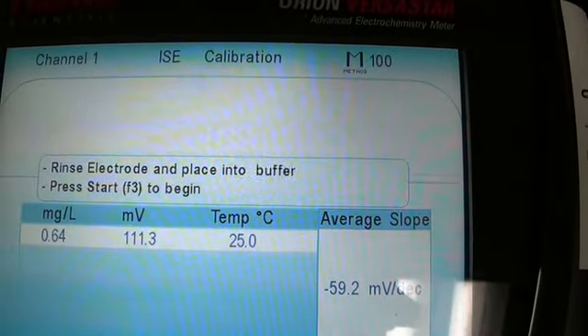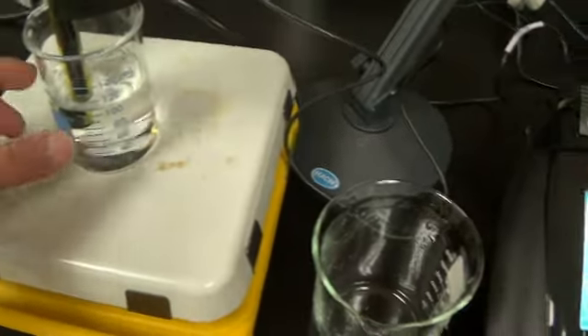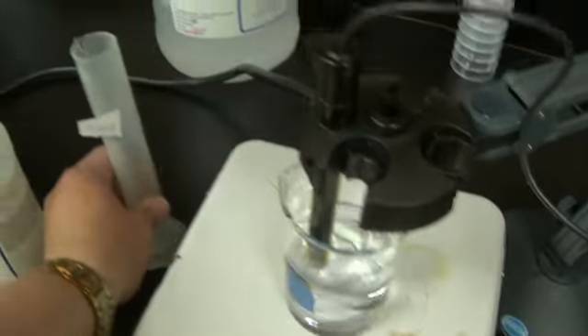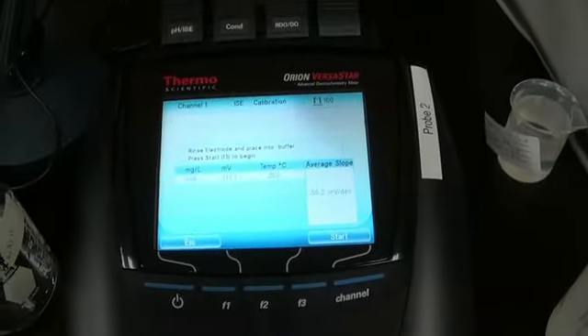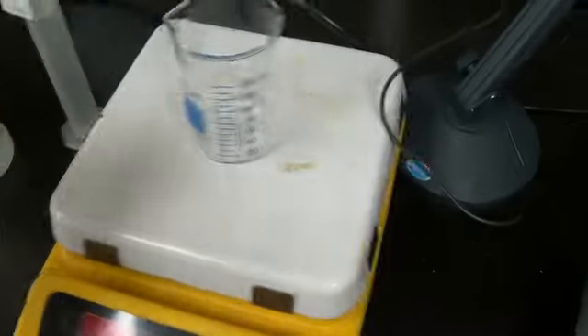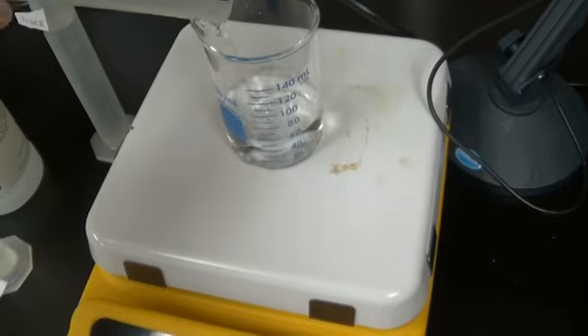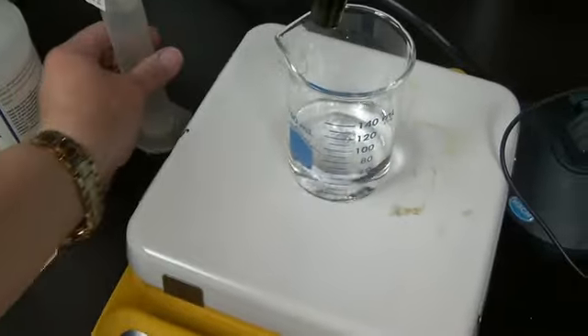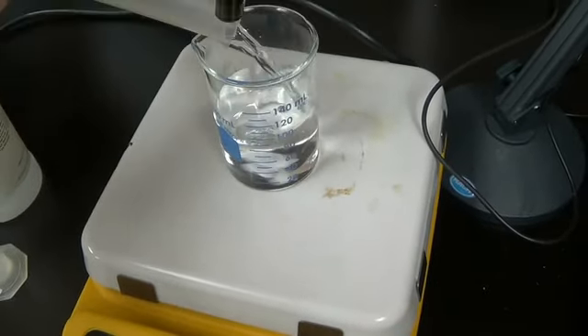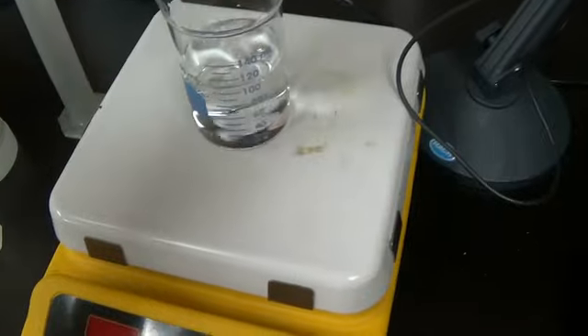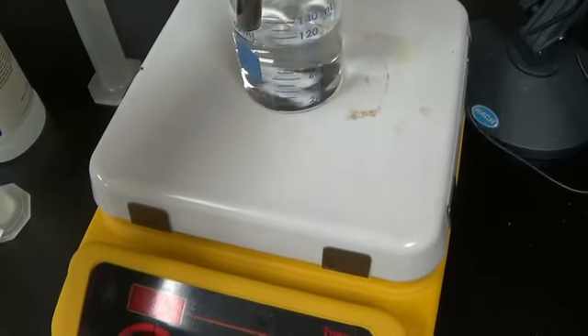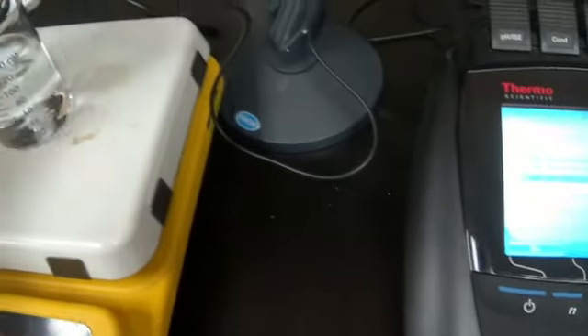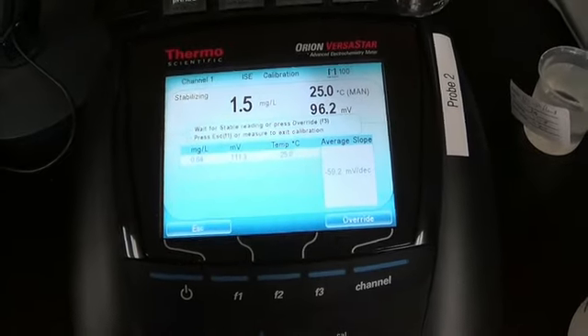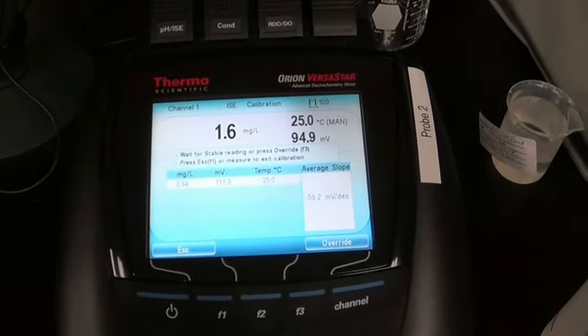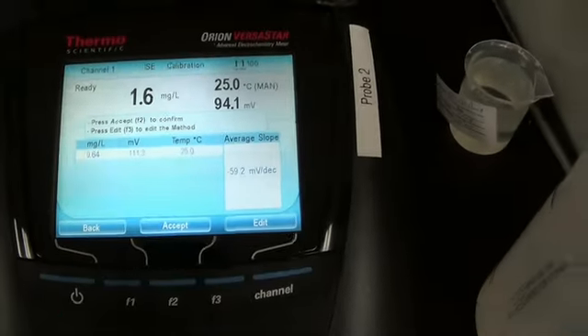So rinse the electrode and place into buffer and press F3 to begin. So I'm going to lift this, put on a new beaker at the 2 ppm, 50 mils of TISAB, and then press F3 to begin. So again, my 2 ppm is next. 50 mils. And start. And wait for it to stabilize again. Oh, it is ready. So I hit accept.